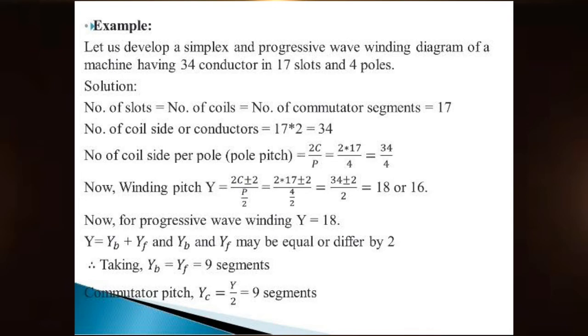Number of coil sides per pole, i.e., pole pitch = 2C/P = 2 × 17 / 4 = 8.5, approximately 8 or 9. Winding pitch Y: the formula is (2C ± 2) / (P/2), which gives 18 or 16. For progressive wave winding, Y = 18. For retrogressive wave winding, Y = 16. Also, Y = YB + YF, and YB and YF may be equal or differ by 2.